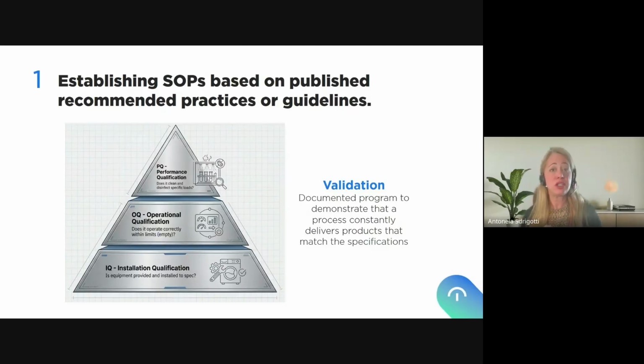Then we have the operational qualification. Does it operate correctly within the limits? This is done with an empty chamber, so we make sure that it operates correctly, but without the load. And last but not least, we have the performance qualification, which asks, does it clean and disinfect specific loads? This is where I have to validate each of my instruments, or at least the most challenging instruments, and perform specific loads to demonstrate that this device is working correctly and cleaning my load correctly.